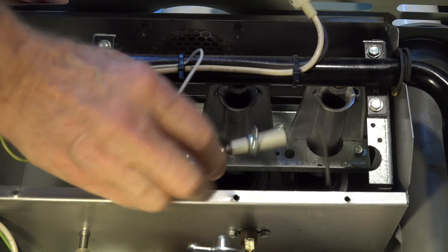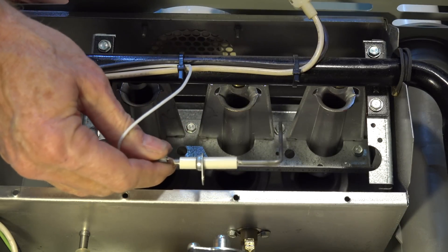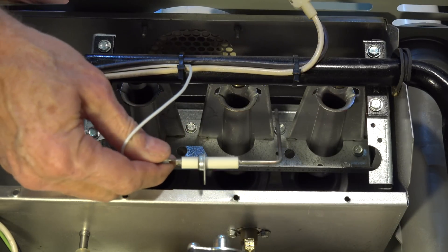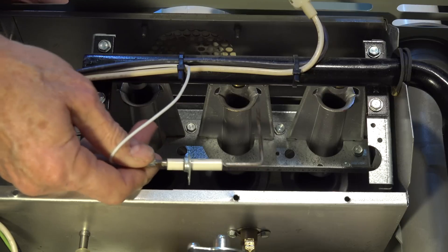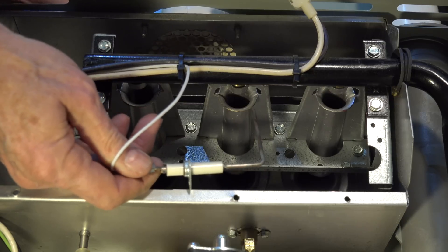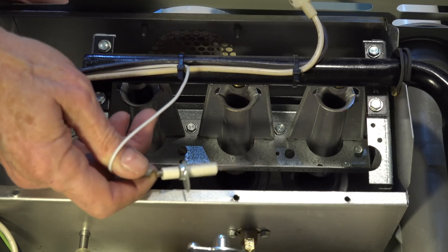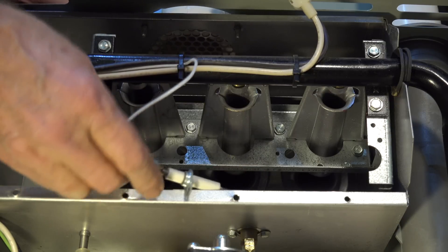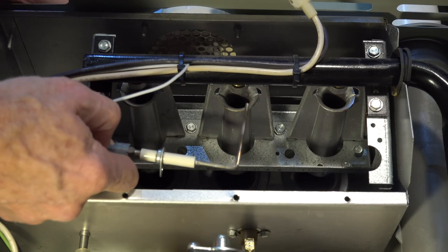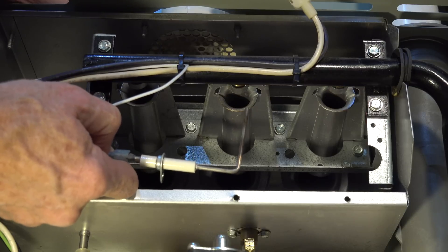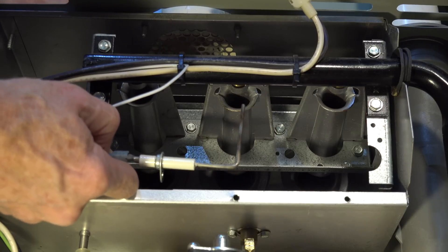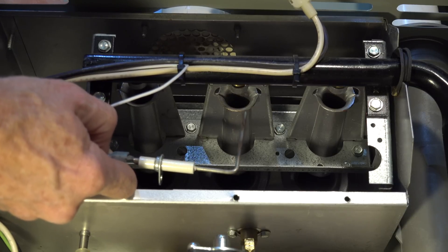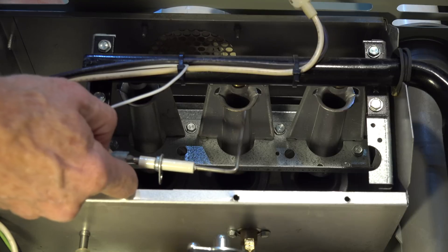Okay, here I've got the flame rod out. Now I will tell you I almost never replace these things. A lot of guys like to do it because they think that'll fix it. It's just a piece of stainless steel. You can use some light sanding and it'll probably sense normally after that. I've got videos on that too.